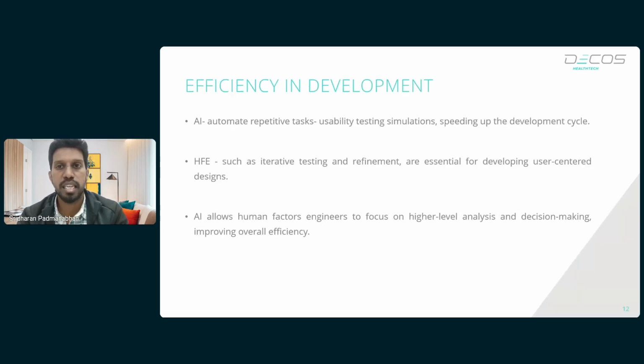And the next is efficiency in development. Whenever we are considering efficiency, there always goes a usability testing for medical devices. Usability testing again would involve multiple factors such as formative and summative, and we go in for multiple refinements during the phases of device design. So whenever a usability failure is identified during a formative study, we come back to the device design phase, refine the design, and then perform the study again. But whenever we are involving AI, it can help us to automate repetitive tasks. So we can bring out a simulated environment, address issues at a very early stage, and then consider the device for a formative study. It can help us to catch design flaws, since coming back and forth again can involve more cost and time.